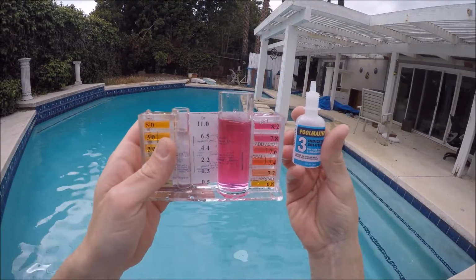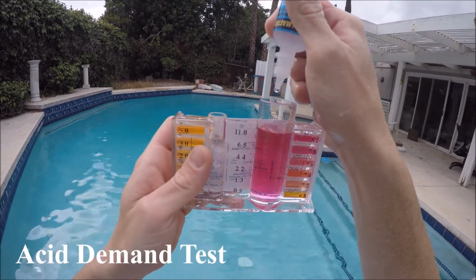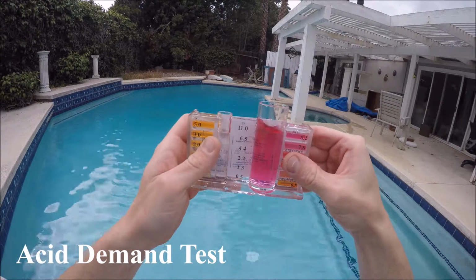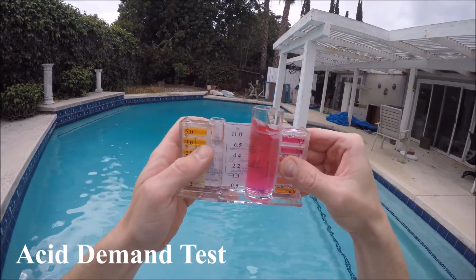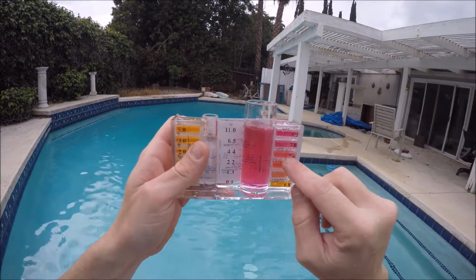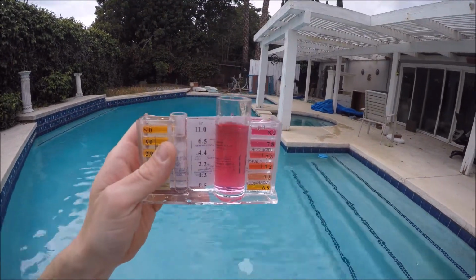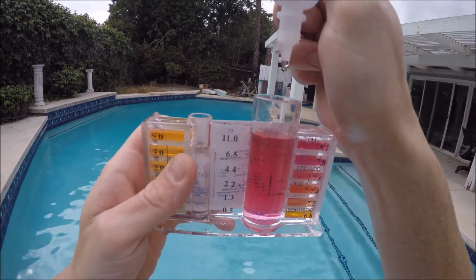We will now test for acid demand using the number 3 reagent. We add a single drop at a time and swirl. This will lighten the pH test reading. We'll do this until we get to the range that we want, which is again 7.4 to 7.6.